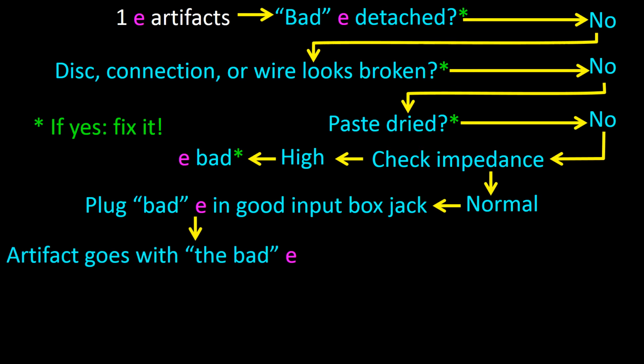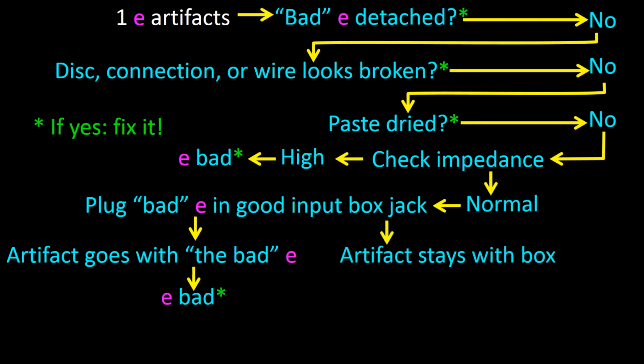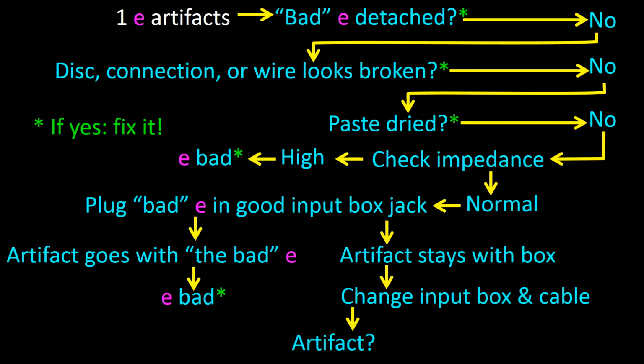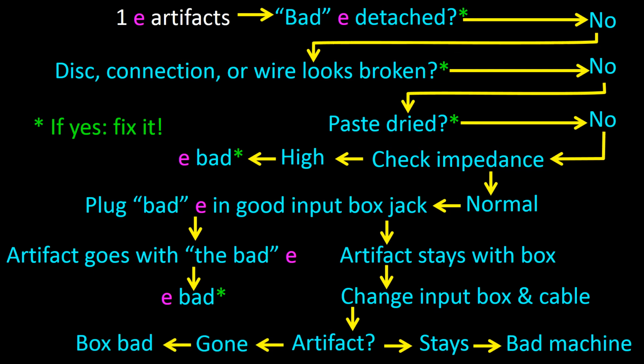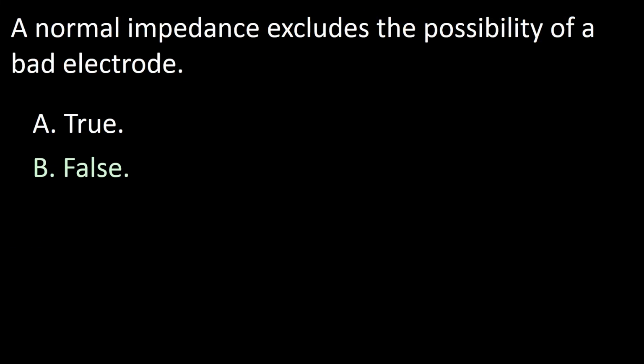If now you see that the artifact is in the location corresponding to the jackbox, where you just put the bad electrode, then the electrode is bad. If the artifact stays with the location present in the box, then you have to change the box and the cable. If the artifact then stays, the problem is with the machine and you need to change the machine. If the problem is gone, then you had a bad box and you fix the problem. So the answer to this question is false.